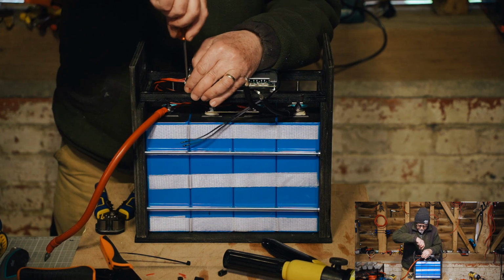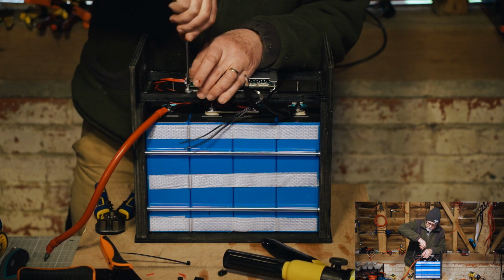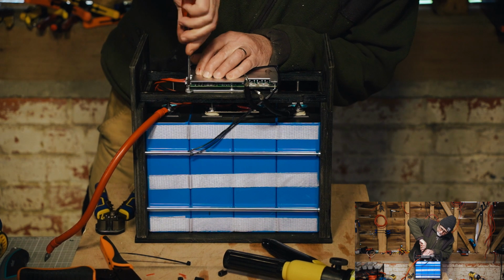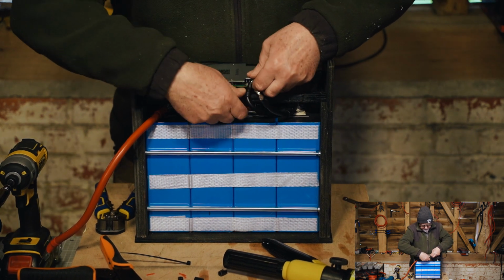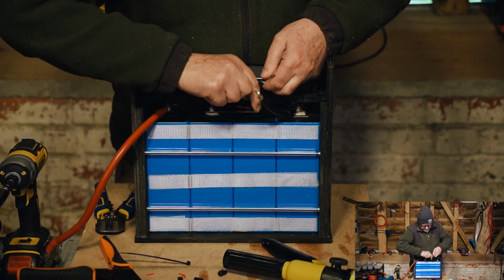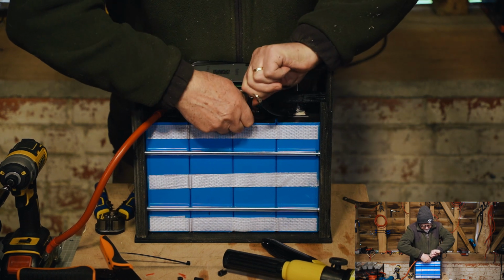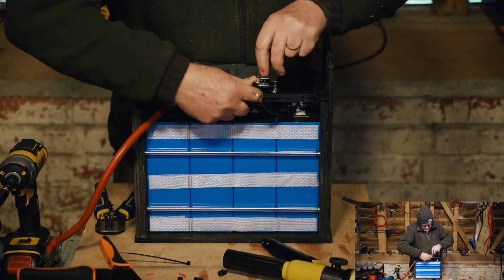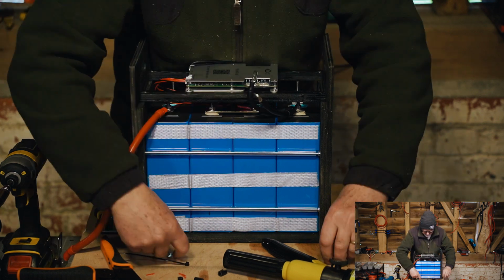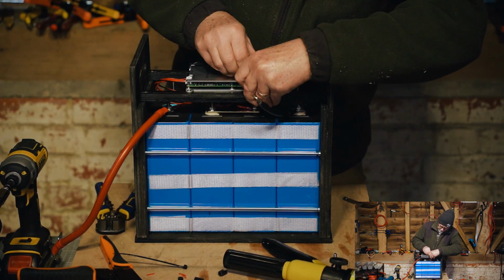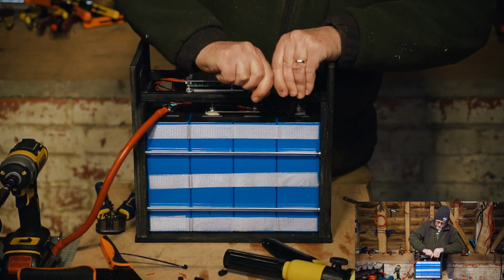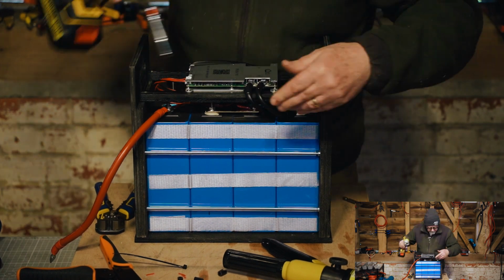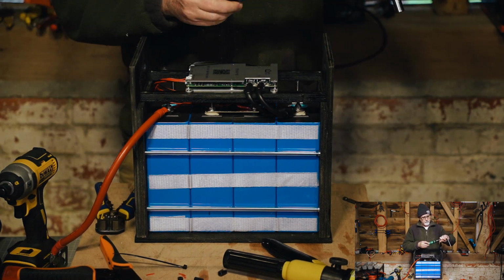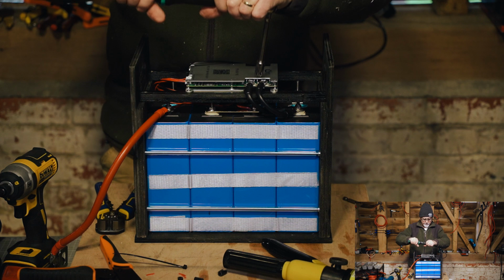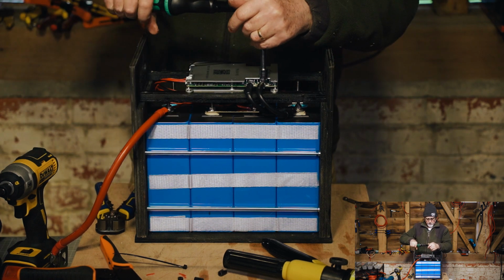Next up is to screw the BMS down onto the bars. We put all 4 screws in, though you could get away with just putting 2 on opposite corners. Then you need to bolt the main wires that go from the B- terminals on the BMS to your actual battery outlet negative terminal. Those we just bolt in with an M6 bolt, and we torque those to around 8 or 10 Newton meters. We've set it at 8, which is where we had it before.